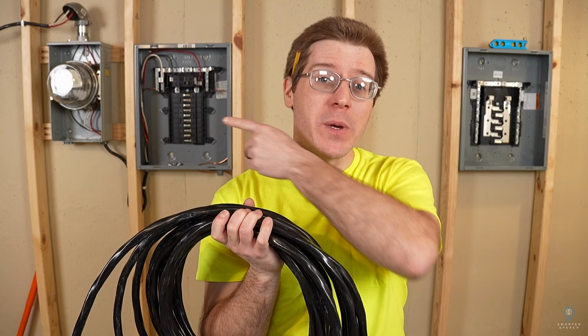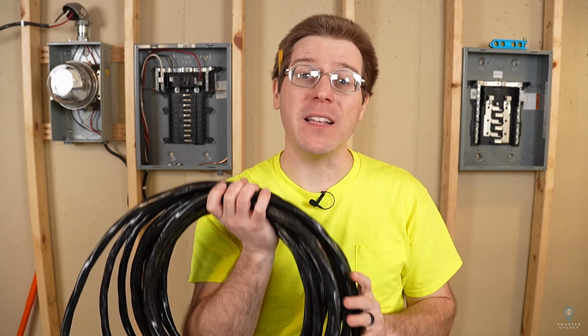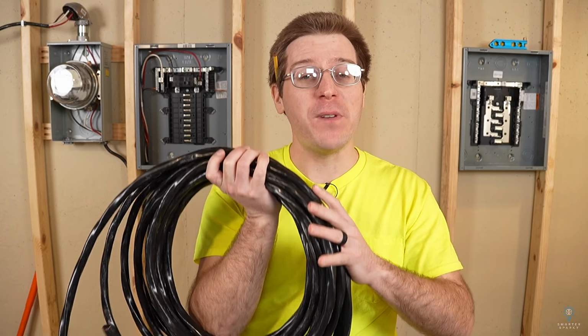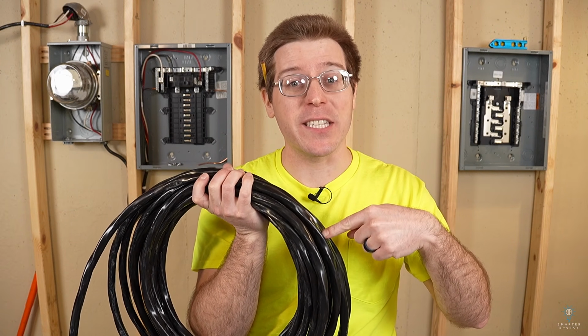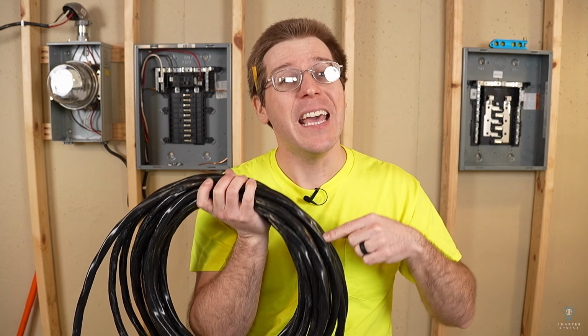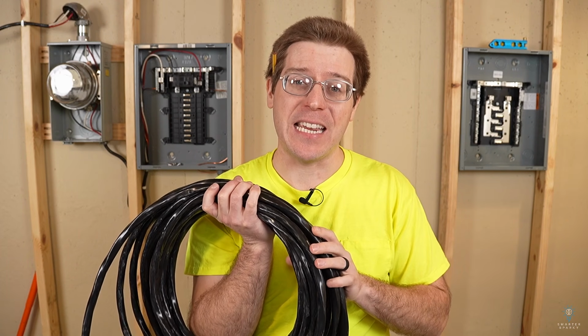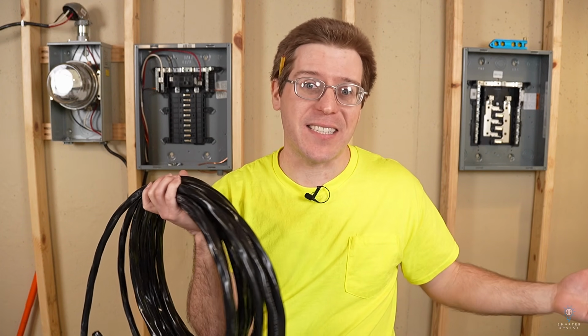The wire going between our main panel and our sub panel is called a feeder. So our feeder in this case is gonna be this 6/3 NM wire, which again is actually only good for 55 amps, but we're gonna be putting it on a 60 amp breaker, which is actually perfectly legal. The reason is 55 amp breakers aren't considered a standard breaker.